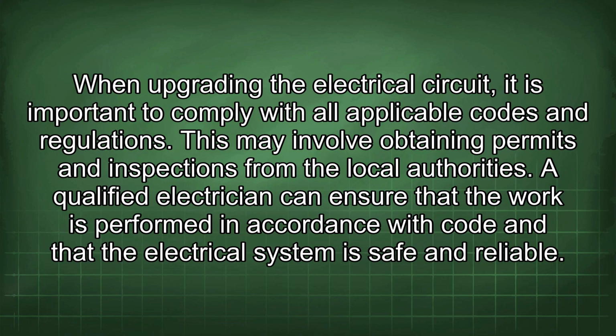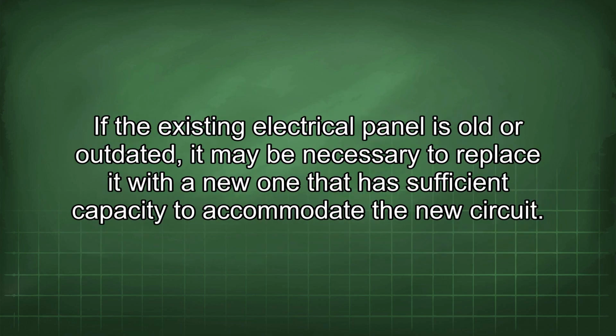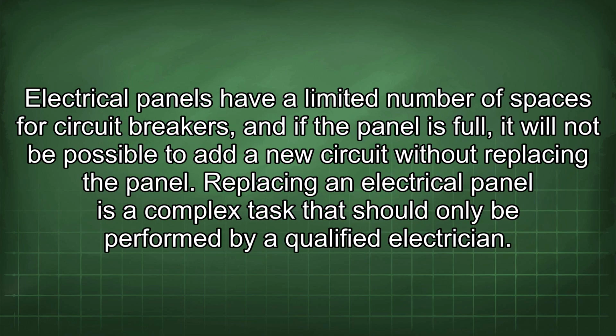When upgrading the electrical circuit, it is important to comply with all applicable codes and regulations. This may involve obtaining permits and inspections from the local authorities. A qualified electrician can ensure that the work is performed in accordance with code and that the electrical system is safe and reliable. If the existing electrical panel is old or outdated, it may be necessary to replace it with a new one that has sufficient capacity to accommodate the new circuit. Electrical panels have a limited number of spaces for circuit breakers, and if the panel is full, it will not be possible to add a new circuit without replacing the panel.